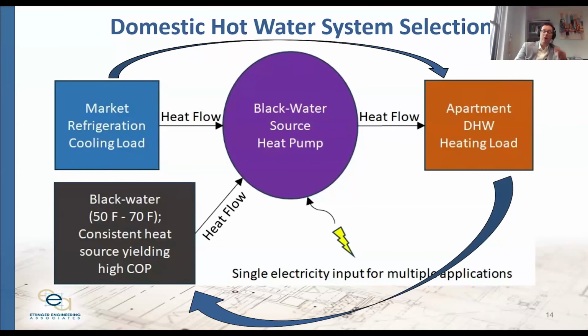We have markets with refrigeration racks for the restaurant stalls down there, and they need constant cooling. Since heat pumps move energy, they're rejecting heat — so let's use that waste heat and send it to the blackwater source stream. And we are: not only are we getting a COP in the high threes, we've pushed the operating efficiency of the system over 4 simply by looking around for waste energy we can use.